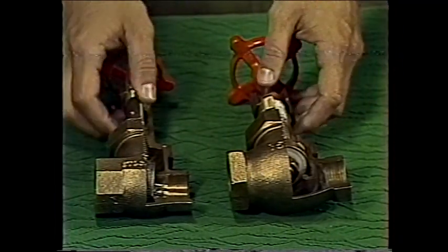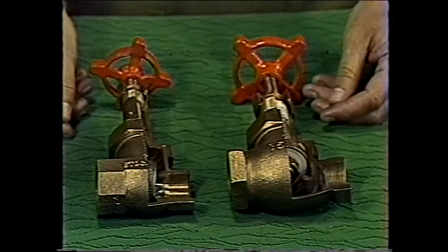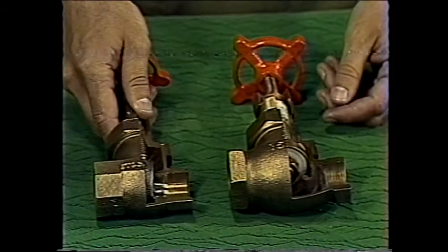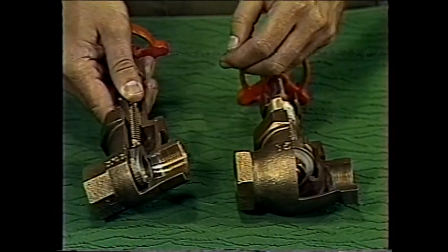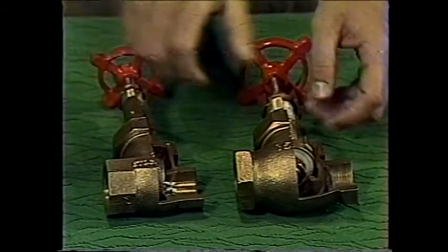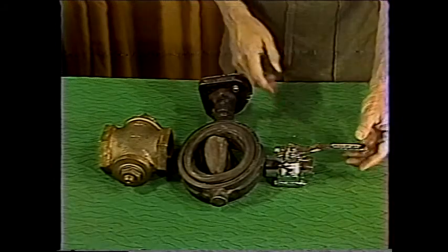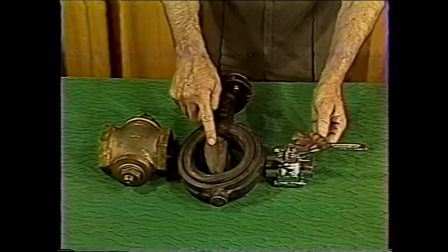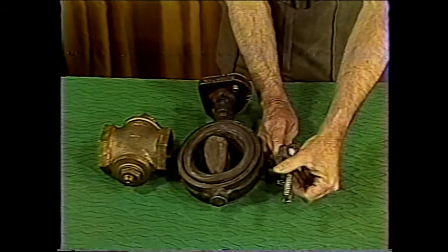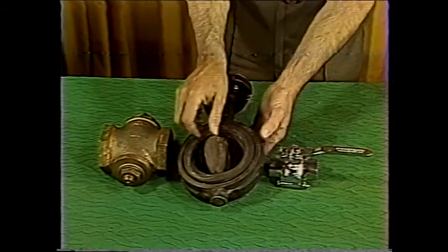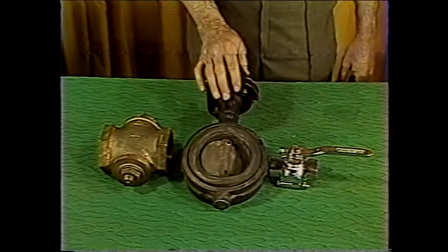Okay, now let's briefly run back over our valves. Gate and globe valves are probably the most common. Gates have little pressure drop but are not recommended for throttling. Globes are used for throttling but have a high pressure drop. Ball, butterfly, and plug valves go from full open to full closed with a 1/4 turn, but the handle and this quick closing may cause water hammer. They have small pressure drop.